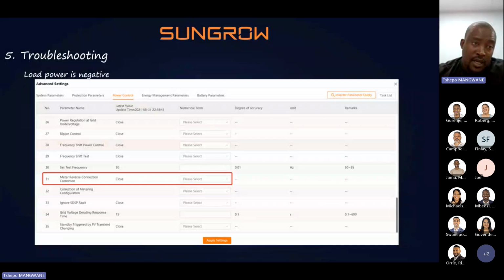Okay, now in this case, our load power is reading in negative. So you will see after installing the system, when you go to your overview, you will see your total consumption has a minus sign on it. We don't need that. The inverter has been supplying power, it is not pulling power from the grid side. So our consumption or our total load should read in positive direction. The moment you pick up that it's reading in a minus direction, just know that the CT on the meter side is facing the wrong side.